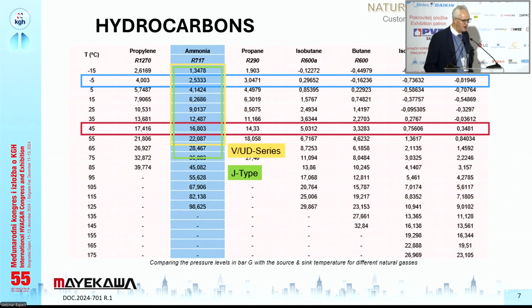I show you just for having a more transparent overview. The first column shows you the temperatures, minus 15 to plus 175. The blue column is ammonia. So if you are using, you see there the yellow square, that are our oldest types we have in operation, V-type and UD type. So there we can go up to nearly 22 bar discharge pressure.